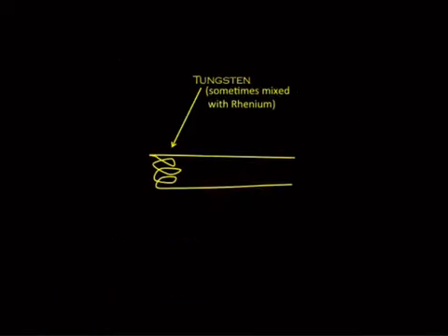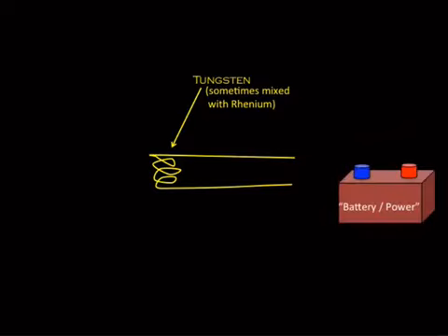All right, so how are X-rays actually generated? Well, they're made by this process called thermionic emission of electrons. Basically, what happens is you take a filament that's made of tungsten. Why is it made of tungsten? There's a couple of reasons, but one of the main ones is that it can tolerate heat. It has a very high melting temperature because it is going to get really, really hot when it gets hooked up to this energy source.